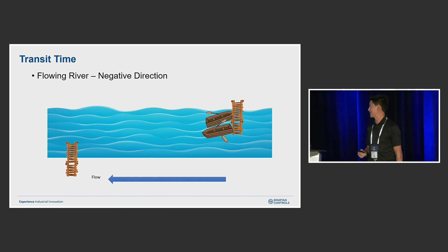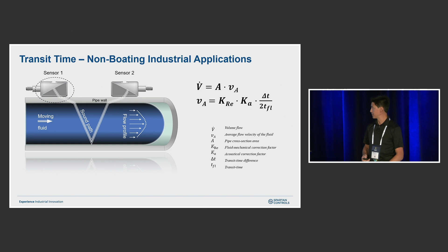For non-boating applications, we use ultrasonics to the same degree. We have a transducer that sends a signal to another transducer, which could be on the same side of the pipe or on opposite sides. The movement with the flow is going to be a lot quicker than the movement against the flow. We plug that into an equation and work out the velocity inside the pipe.